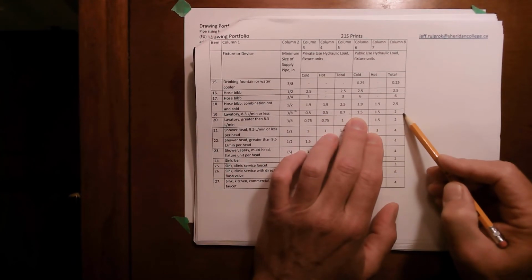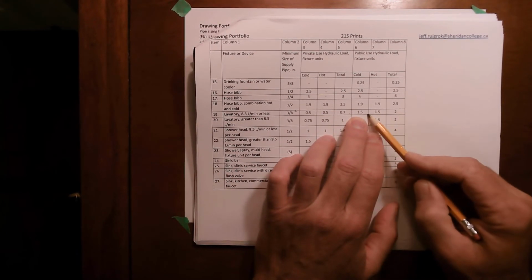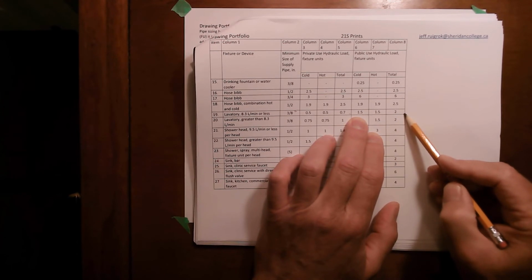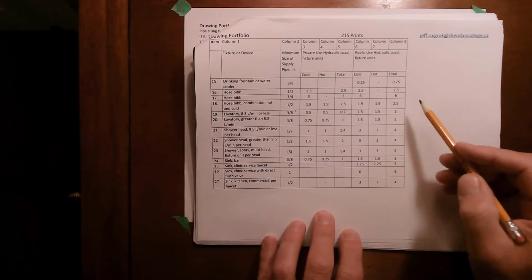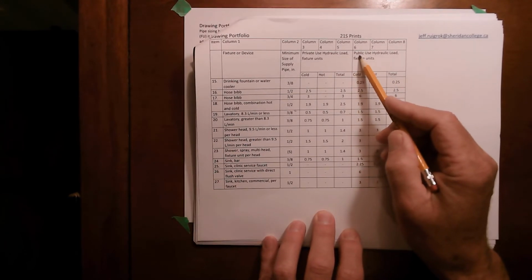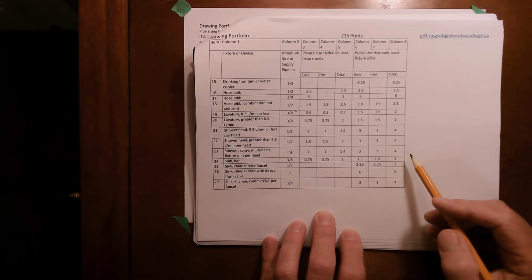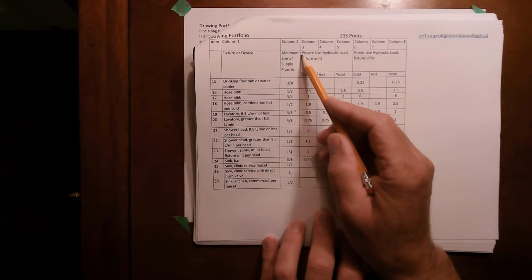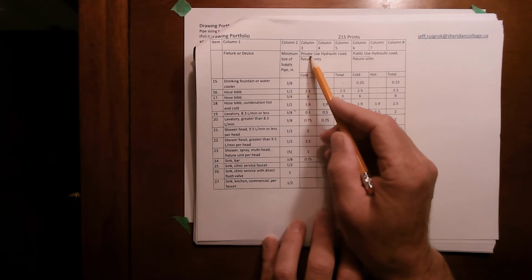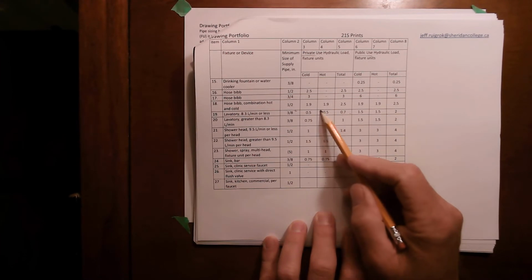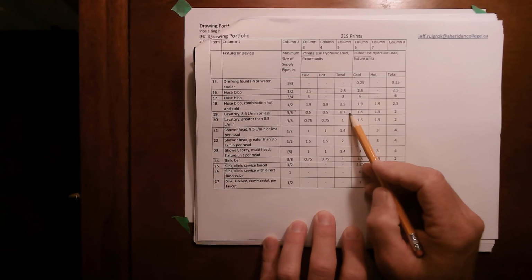Now, when you go over to the next three, you'll see you've got cold load of 1.5, hot load of 1.5, and a total load of 2. But it's important to remember that this is for public use. So that would be libraries, hospitals, schools, things like that. And we're just trying to stick with the residential stuff where possible. So that would be the private use, or dwelling, sometimes called. So we're sticking with the smallest one where possible.